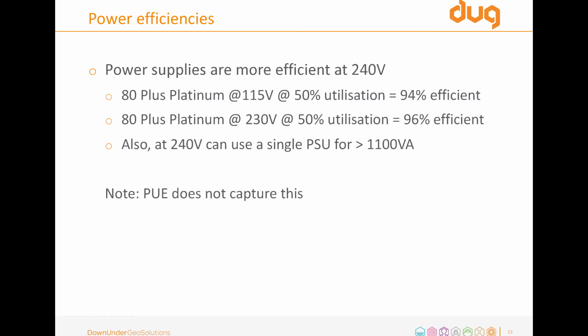The other main driver for this is that if you run at 240 volts, you can get 2.5 kilowatts out of your power supply. So most of your nodes you can run on one PSU. At 110 volts, you can only get 1.1 kilowatts out of your PSU. So you have to have 2 power supplies on to keep your nodes up. So this change to 240 volts drove an efficiency and also drove a practicality in trying to reduce the number of cables in the data centre.